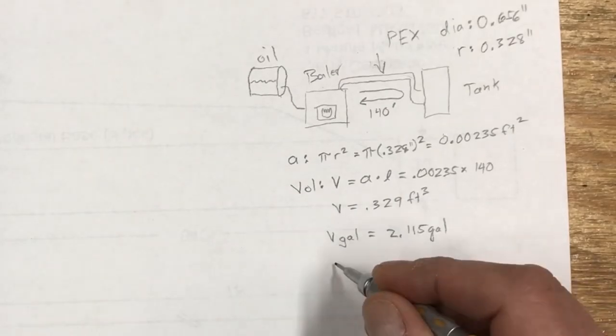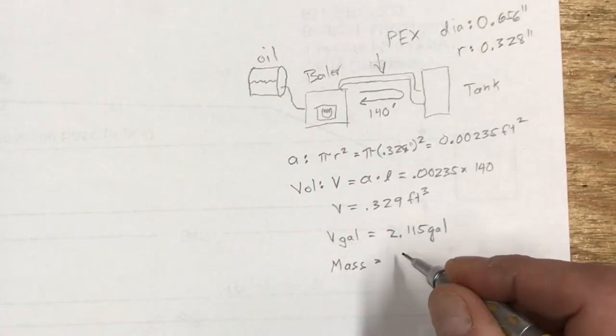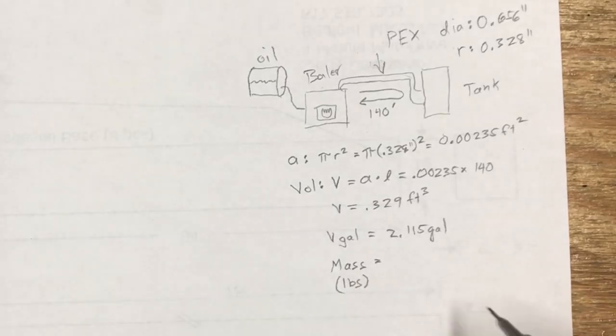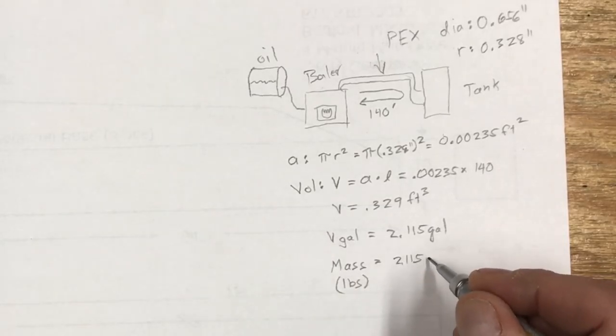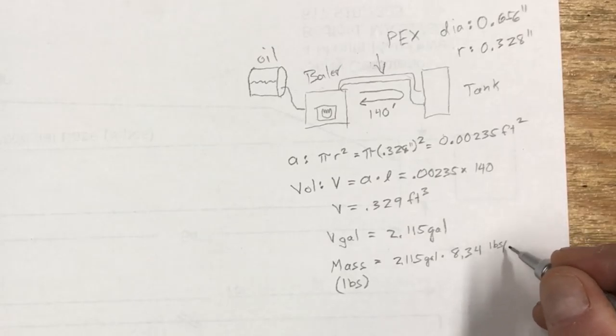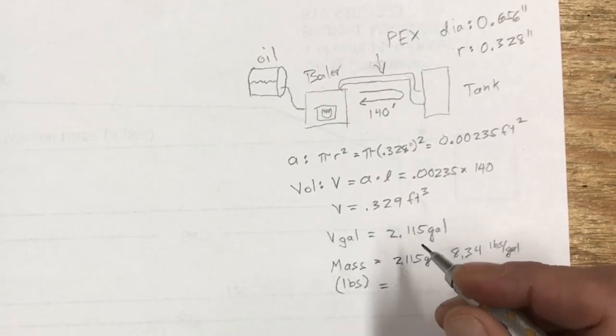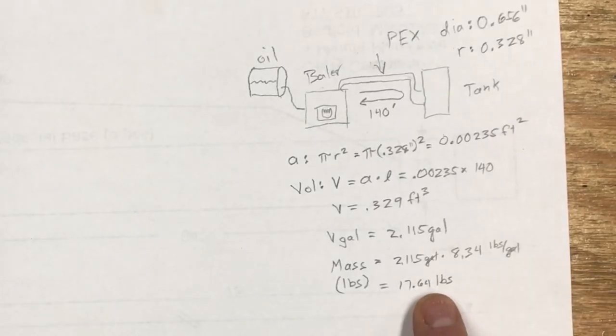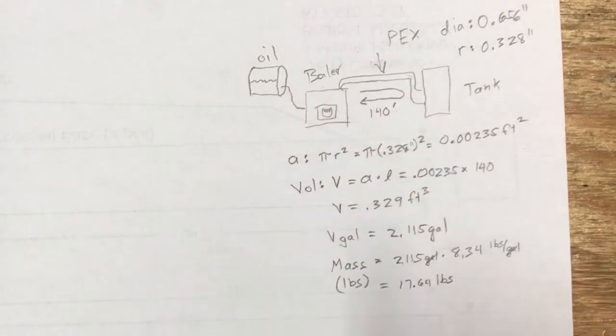So the mass of the water and this is in pounds again, sorry for those of you out there not in the metric world, is 2.115 gallons times 8.34, this is pounds per gallon. The gallon units cancel each other and you end up with a mass of 17.64 pounds. So there's about 17 and a half pounds of water in these PEX tubes all the time.